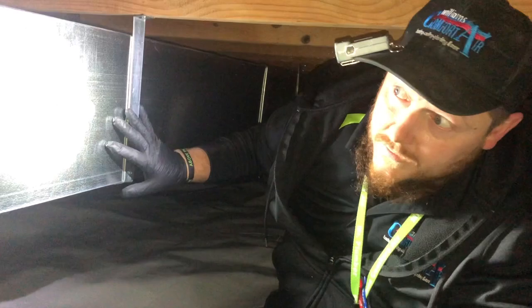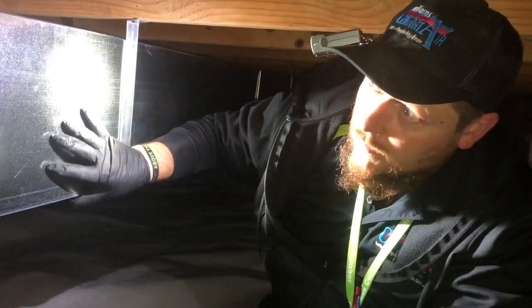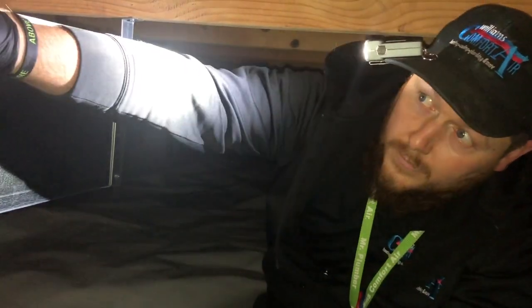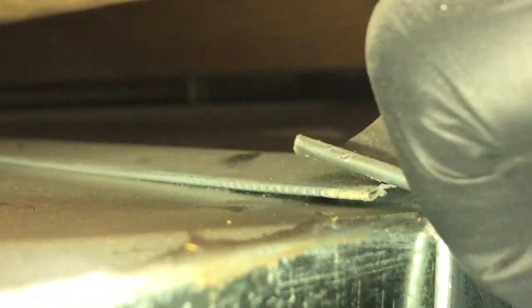Once we were done with all the ductwork and verified that everything was installed as we wanted it to be, we opened up all of our different dampers throughout the duct system, and then we sealed the entire duct system. So here you can actually see where the duct is coming together, right up top here, right off of our takeoff where we put a screw in, and how we actually sealed the duct system with our AeroSeal process. And if you look down here, even on the regular drive, it's bent over, you can actually see the sealant of everything being sealed up.